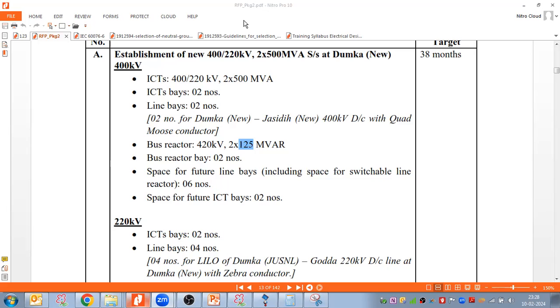Hello, can I say something to Saurav if you don't mind? Saurav, actually I was working at a 400 kV grid substation. It was our duty to inform the load dispatch center that our bus voltage is increasing. Then they used to issue us a code, speak with the National Grid Center, take a code, and then give us permission to put our bus reactor into service. We used to do it remotely. That's the procedure followed at the grid substation.